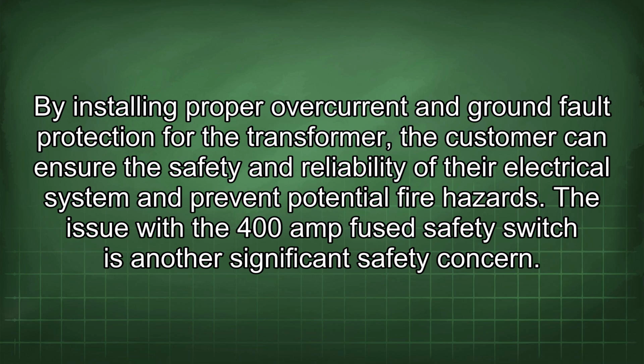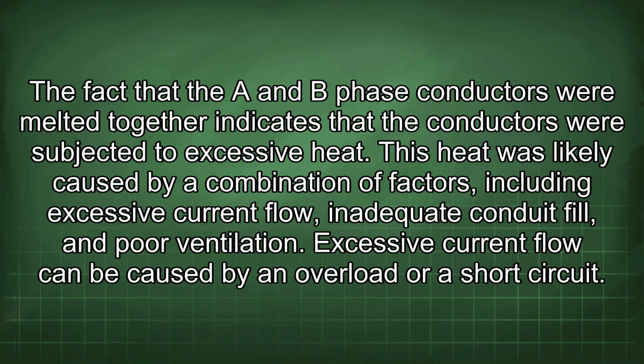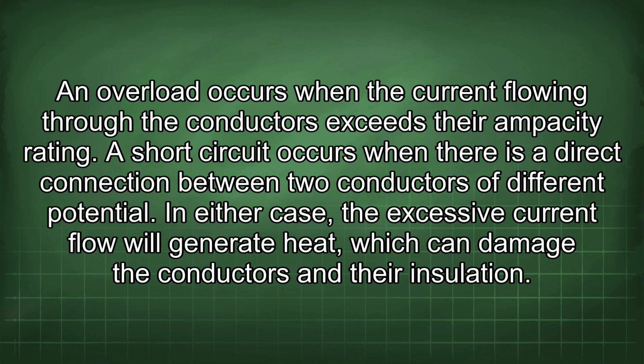The issue with the 400 amp fused safety switch is another significant safety concern. The fact that the A and B phase conductors were melted together indicates that the conductors were subjected to excessive heat. This heat was likely caused by a combination of factors, including excessive current flow, inadequate conduit fill, and poor ventilation. Excessive current flow can be caused by an overload or a short circuit. An overload occurs when the current flowing through the conductors exceeds their ampacity rating. A short circuit occurs when there is a direct connection between two conductors of different potential. In either case, the excessive current flow will generate heat, which can damage the conductors and their insulation.